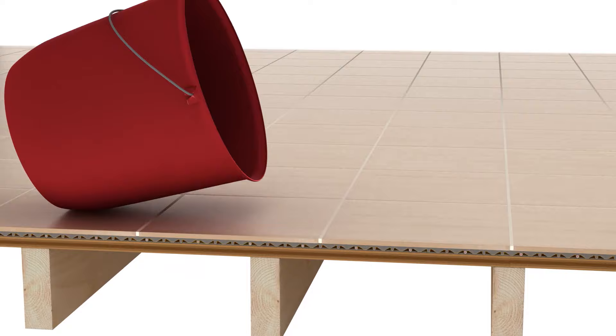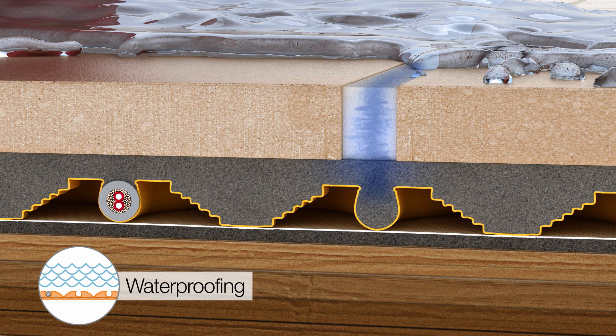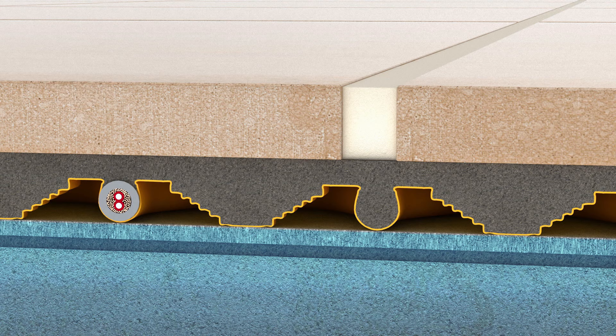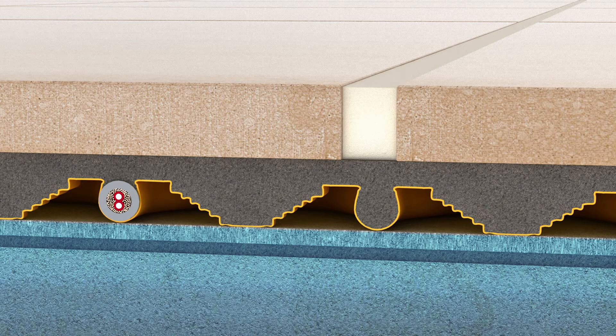Tile coverings are not waterproof, and water can get through the tile covering to the substrate below. DITRA-HEAT and DITRA-HEAT DUO provide reliable waterproofing to protect moisture-sensitive substrates from water exposure. The free space on the underside of the membranes provides a route for excess moisture and vapor to escape from the substrate. This vapor management function allows for tile installation over concrete cured less than 28 days and concrete on grade passing vapor.